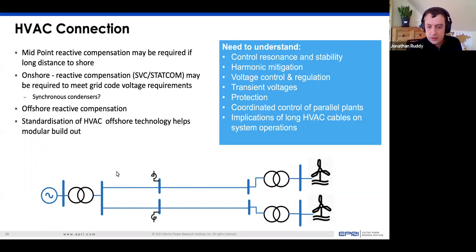Where the system becomes more challenging is if you have multiple AC connected plants coming into the same point of connection or nearby points of connection onshore. Then you need to consider how those interact with each other and how the voltage control in particular can be coordinated across the parallel plants. There are a number of things there that need to be looked at from the system planning point of view. Standardization has really helped to build this out and to improve this. AC connected wind farms can be built in chunks at standard voltage levels and standard power levels, and that's really helped to drive the cost down and help that modular build out.